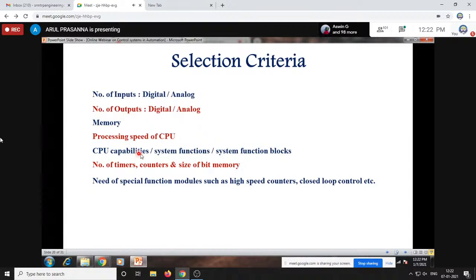What are the additional functionalities, the CPU capabilities? Some system blocks and system function blocks are available. Comparing to previous versions of PLCs, system function blocks were not available, so we had to mention a timer with a particular address and a counter with a particular address, which may cause a mismatch where the program doesn't execute exactly. To avoid that, CPU capabilities are now enhanced with system function blocks, which are predefined functions with certain functionalities already loaded inside. How a timer has to work, we don't define ourselves, it's already preloaded. We just drag and drop the timer and make it work for our particular process.